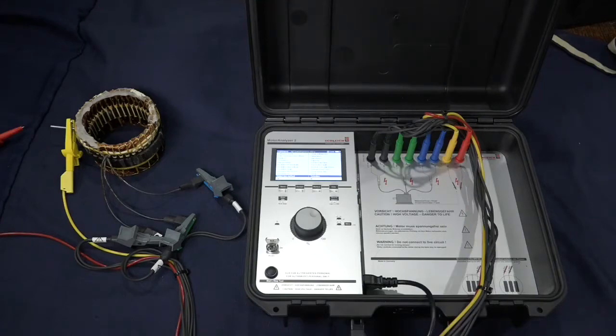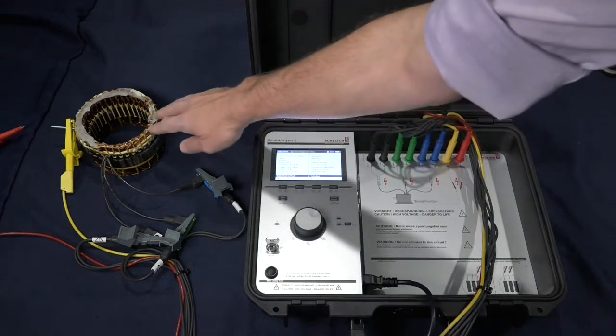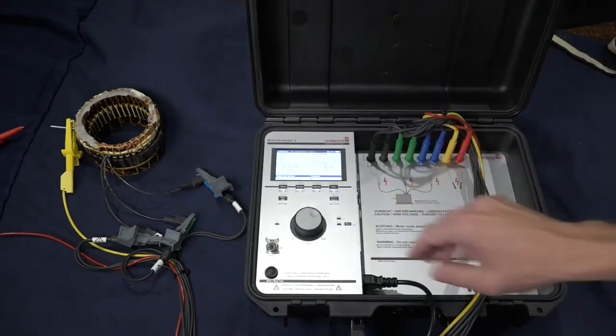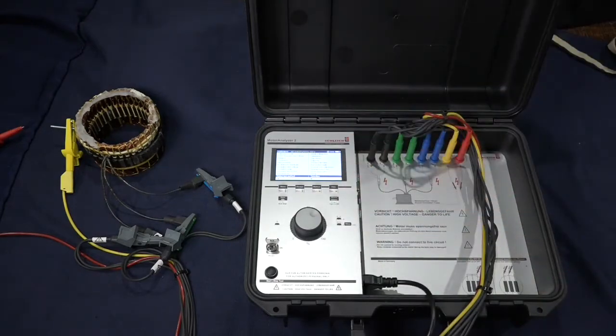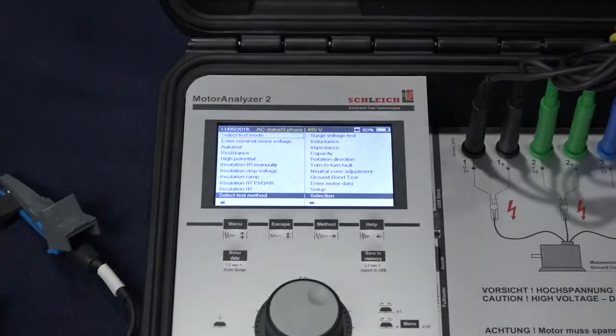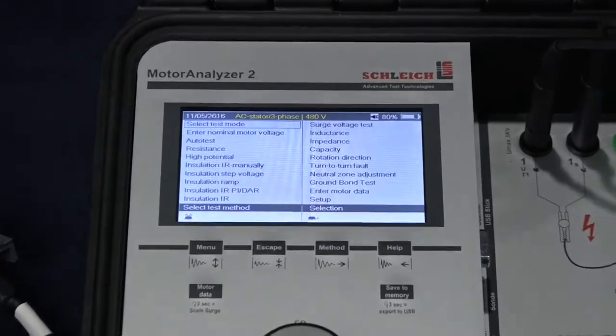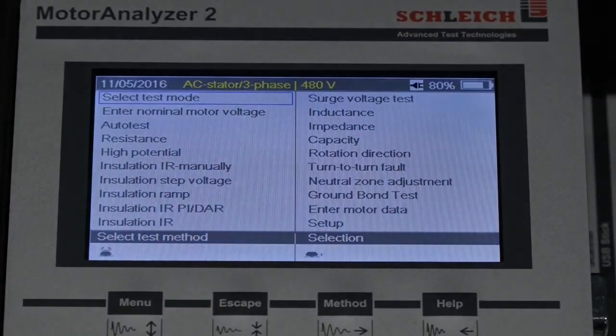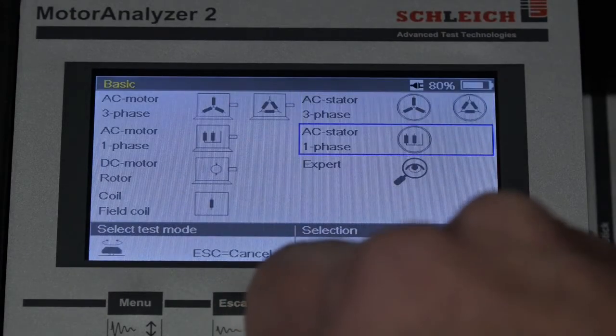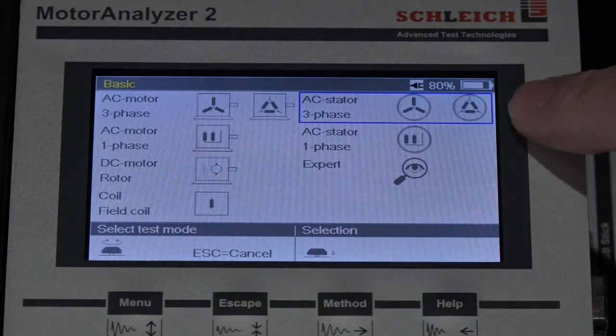So we've tested an assembled motor. Let's test a stator. So over here on the left side, you can see I've replaced our motor with a small stator. Over here on the screen, let's zoom in and I'll show you the settings for testing a stator. The upper left-hand corner, let's enter this select the test mode item, and we'll move this thing, the whiz wheel, over to select the AC stator 3-phase.